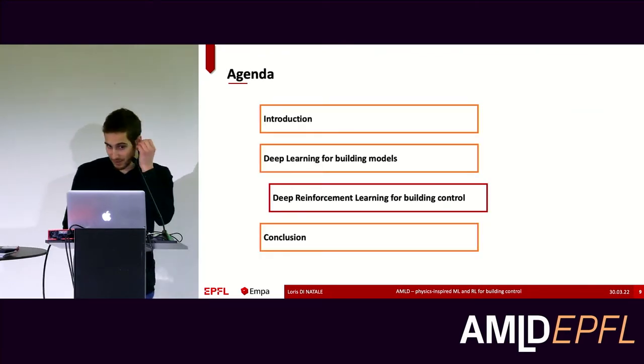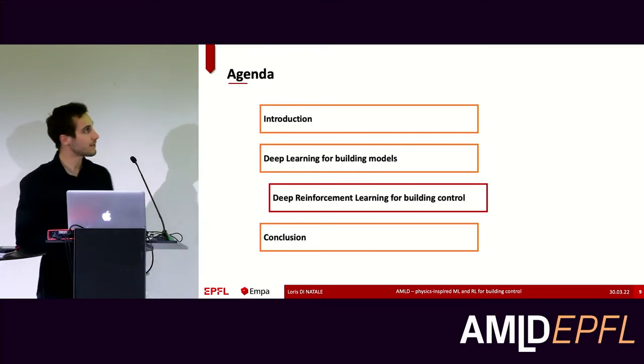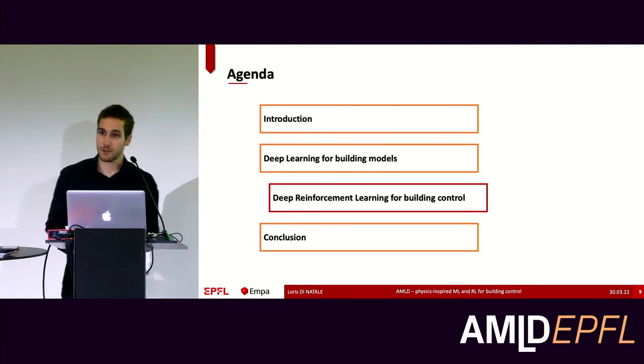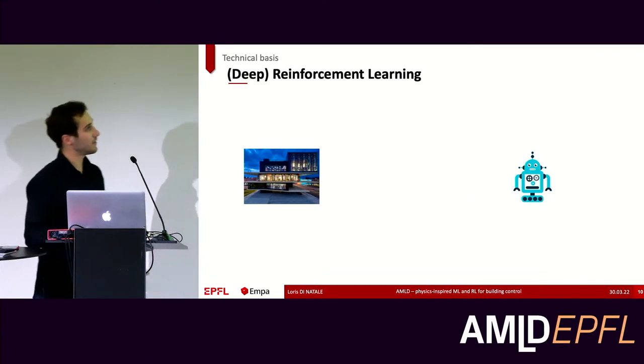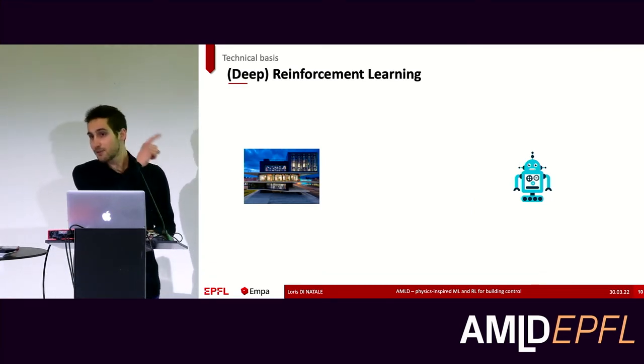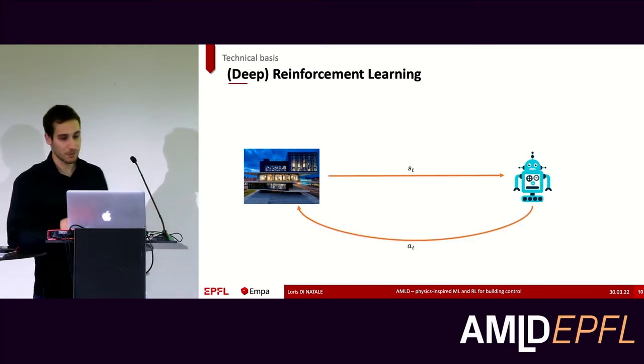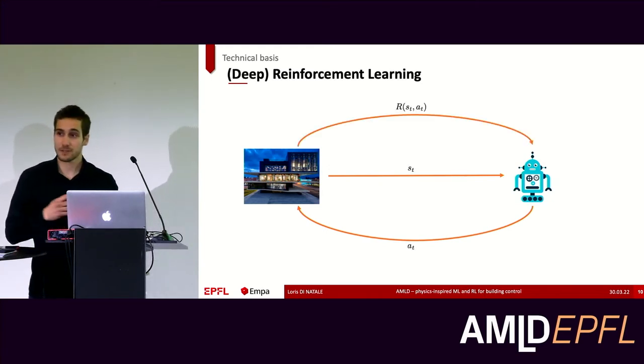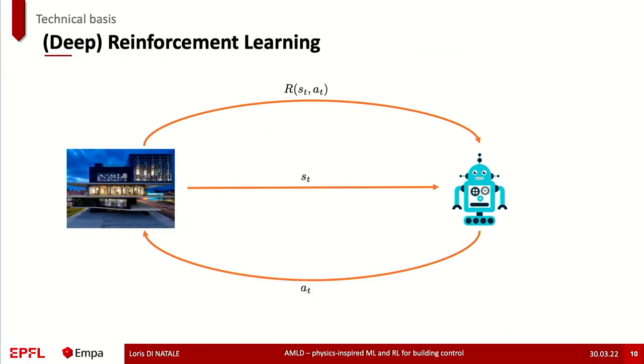Now that we have the models, we can look at how to use them to actually save energy in the real world. We propose to use deep reinforcement learning, which is just one of many control techniques that can be used. The way it works is that you have an agent interacting with your building. At each time step, the agent observes what's happening, decides what to do, and is rewarded for it. We tell the agent how good or bad its decisions were, and by iteratively interacting with the building, the agent learns to maximize the reward and take the best actions possible.